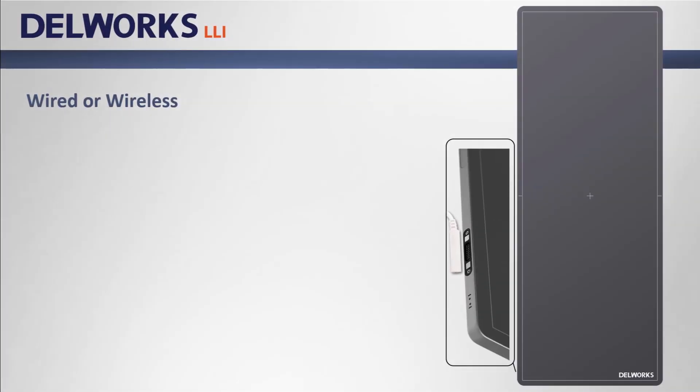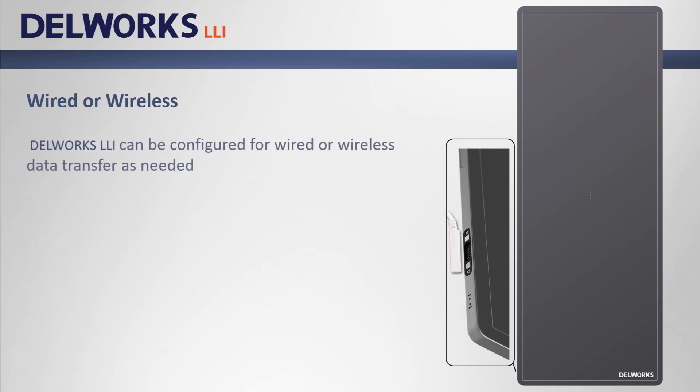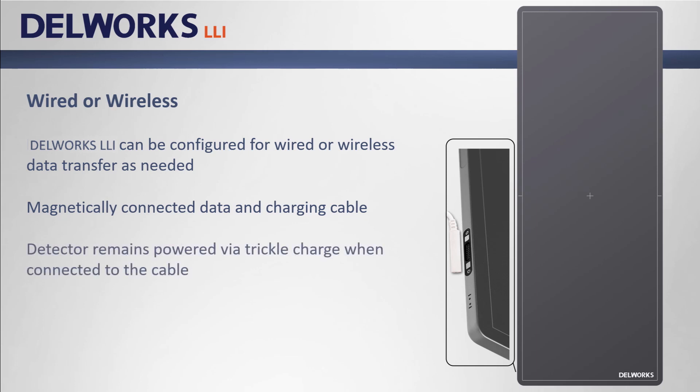Delworks LLI can be configured for both wired or wireless data transfer as needed. It includes a magnetically connected data and charging cable that can be quickly and easily removed if needed to use the panel on the table or in the operating room. The detector remains powered by a trickle charge when connected to the cable.